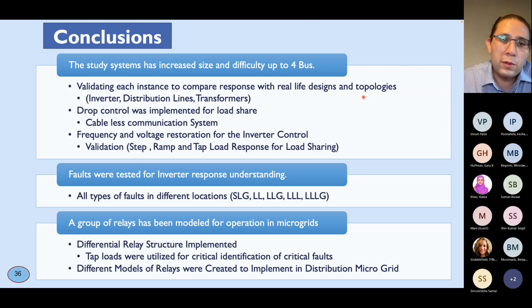We implemented droop control for sharing the load without communication. It's a very efficient way to coordinate between inverters, all of which are voltage source type inverters, the common kind we can buy anywhere. We were able to test that the frequency and the voltage are kept as the norms expect, whether we have a load, whether we have a fault, or when we return to normal operation, and we follow the critical times.